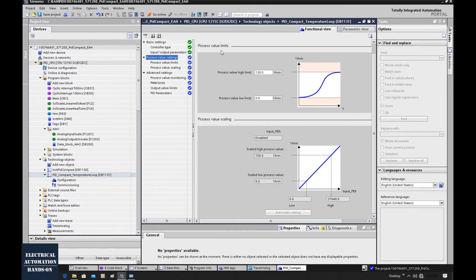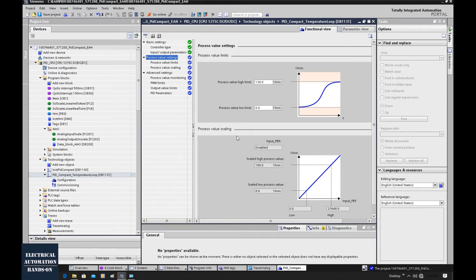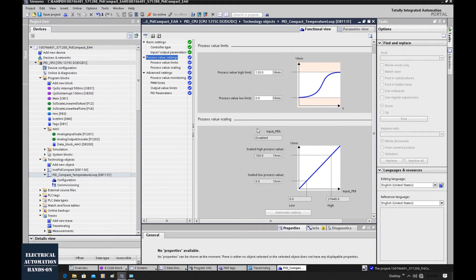For process limitations, usually we will set individual logic — and in most cases we will set additional logic outside the PID loop. Also, if you are going to use internal scaling for the analog input, you can enable the input_PER. But in our case, we are using a program from outside to scale the analog input, so we will not use any setting here and will leave all of them as default.